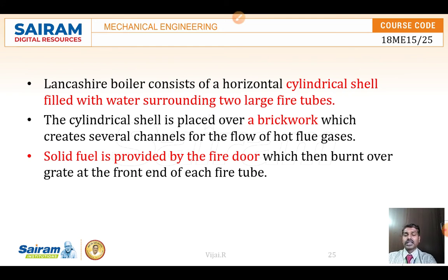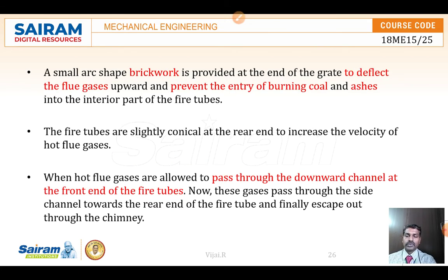Now we are concentrating only on the Lancashire boiler. It is a cylindrical shell filled with water, and there are two large fire tubes through which the hot flue gases are going to pass. The solid fuel we are burning at one fire door, the door where we are firing that fuel. The brickwork is provided to deflect the flue gases and to prevent the entry of burning fuel and ashes into the interior parts of the tubes.